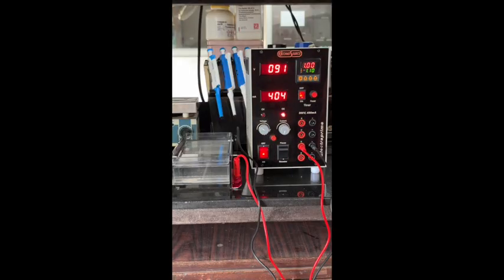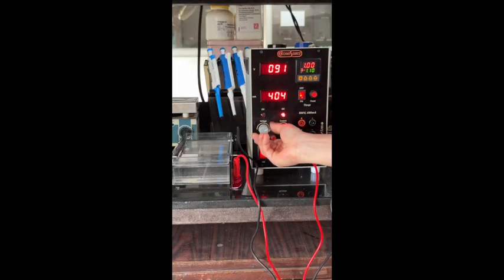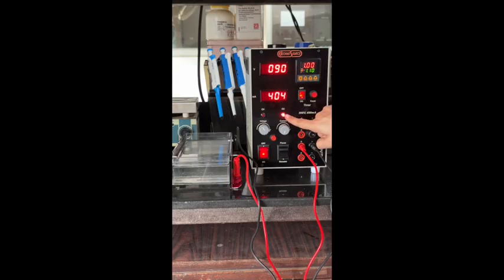Indication 5. Cannot set voltage to a desired value. This happens when there are high current values exceeding the limit that is set or the capacity of the power supply, due to which the power supply has switched to the CC mode. This can be confirmed by checking if the LED indicator for CC is lit up.